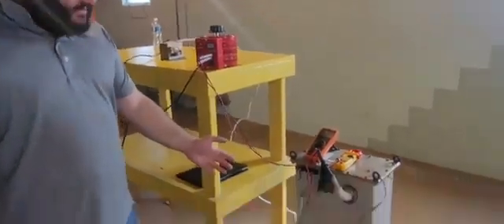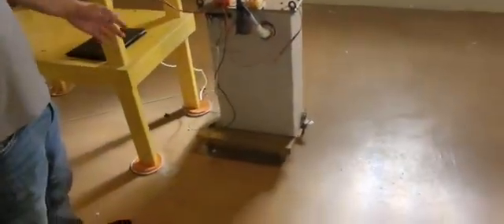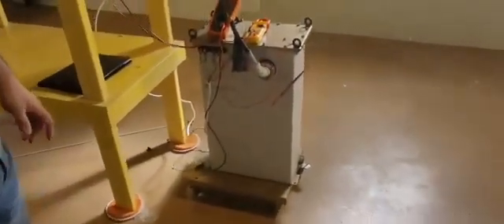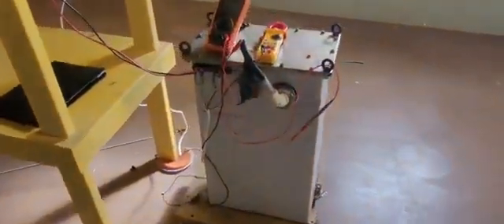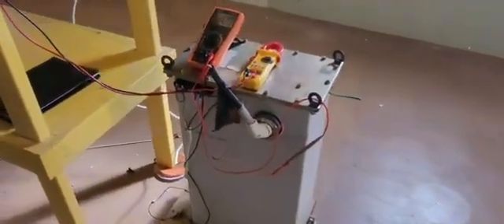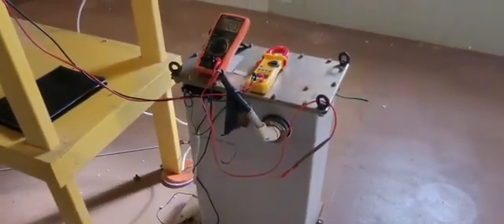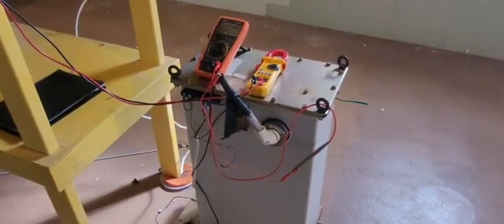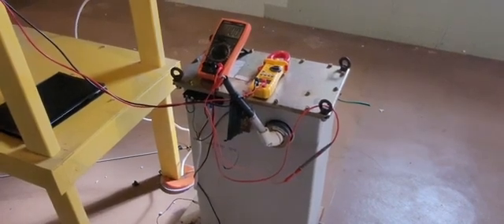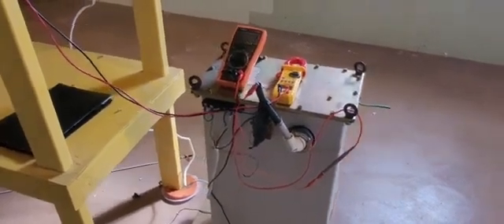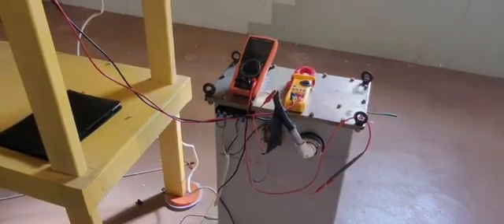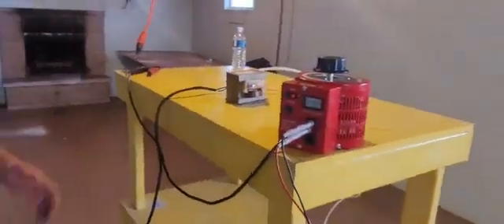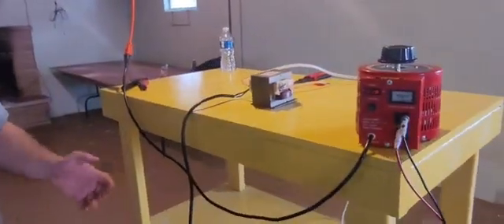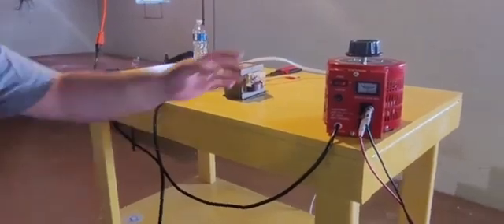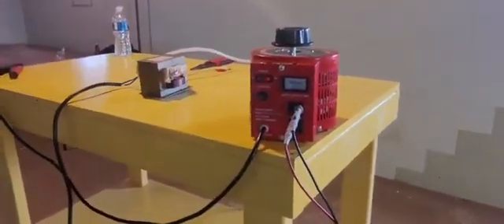And this is just the power supply for one. This particular one is a Philips, made 1987, I believe. It was used out of an X-ray machine, but is now spare parts, and it does work. This particular one will go up to 80,000 volts, 80 kilovolts at full power. And I'll be powering it again with a variac. For this test, in the beginning of the video, we're just going to power it with the residual voltage coming out of the variac, which is about 0.6 volts AC.